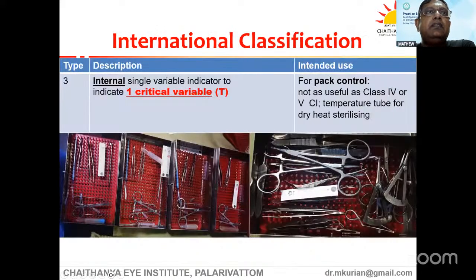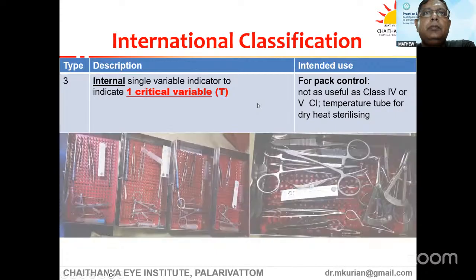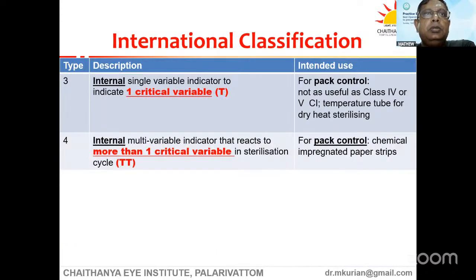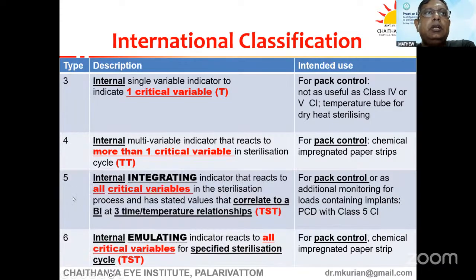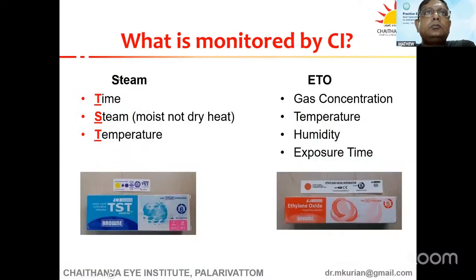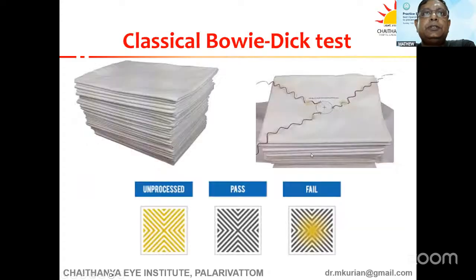So here we have the internal indicator sitting there, and this is for pack control because it gives only one critical variable has been achieved. Class 4 is showing more than one critical variable, and class 5 and 6, integrating and emulating, show that TST, temperature, steam, time, all have been achieved, and these are used for pack control. So what is monitored by these chemical indicators? Temperature, steam, time, and for ETO, gas concentration, temperature, humidity, and the exposure duration.